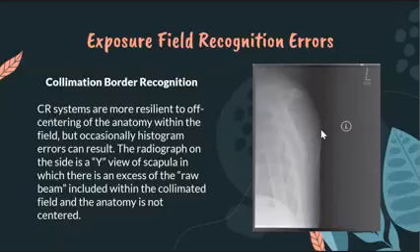This resulted in a histogram analysis error and a dark image because more than half of the image is background density. Remember the example I told you about the flashlight? If you image with half of the image being background densities, the histogram analysis will be thrown off, and of course the quality of the image.